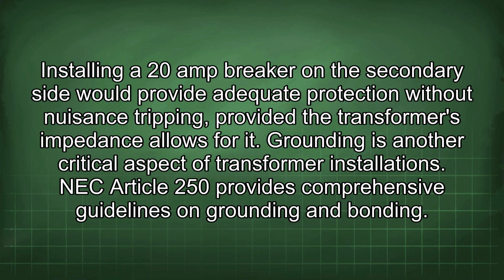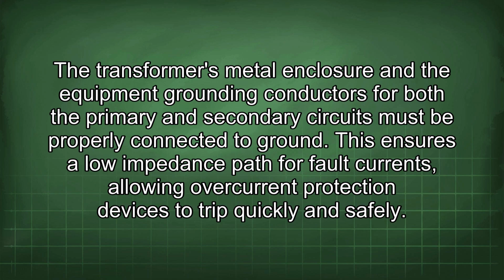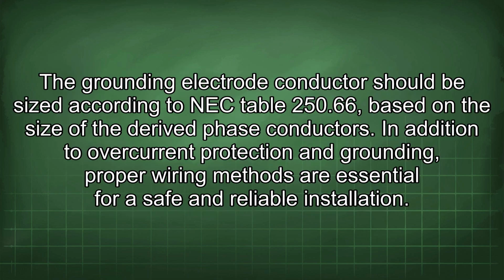NEC Article 250 provides comprehensive guidelines on grounding and bonding. The transformer's metal enclosure and the equipment grounding conductors for both the primary and secondary circuits must be properly connected to ground. This ensures a low impedance path for fault current, allowing overcurrent protection devices to trip quickly and safely. The grounding electrode conductor should be sized according to NEC Table 250.66, based on the size of the derived phase conductors.